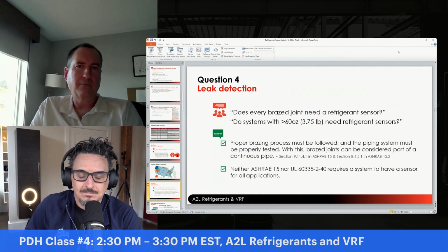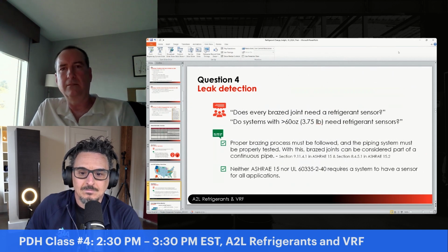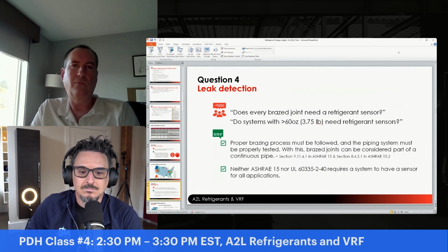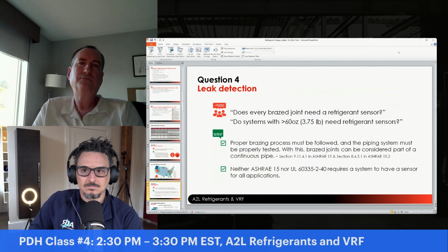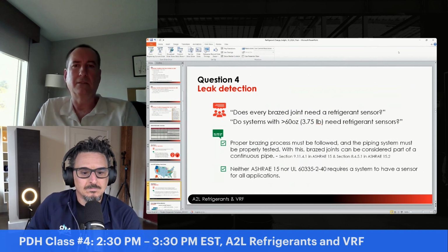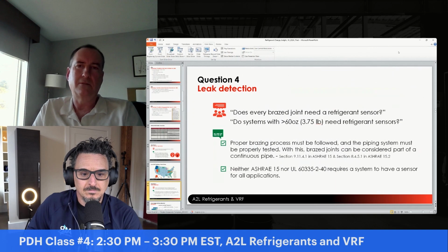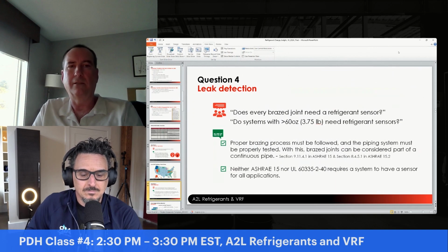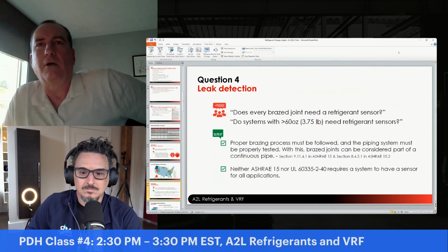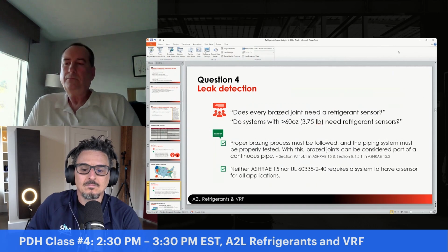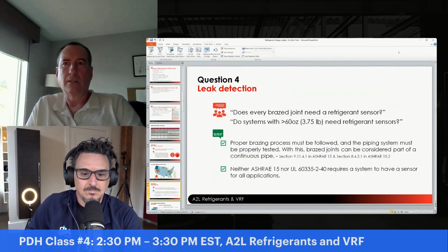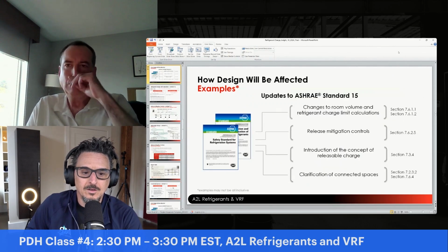Per code, if you do your proper brazing techniques and do what you're supposed to do, a braze joint is considered just part of one continuous pipe. So no, you do not need sensors everywhere, and neither of the standards, ASHRAE or UL, require a system to have a sensor for all applications. That's good to know.